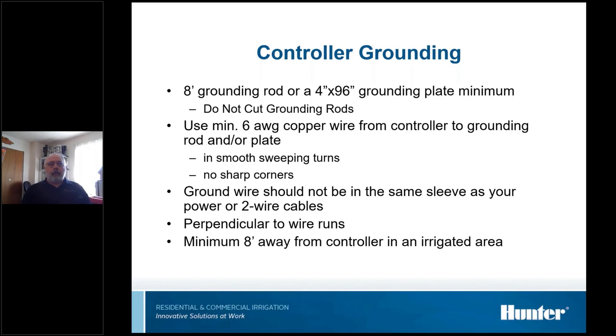Again, 8 feet away from the controller, that's just a given. We're using 8 foot rods and 8 foot plates, so you need to be at least 8 foot away to get outside of that sphere of influence. This is just a diagram of how you would do a controller where we're doing a rod and a plate together, and this is common in different areas. But the main thing is that we need to stay perpendicular to the wire path, put as far away as we possibly can get. We want to keep everything apart from each other.